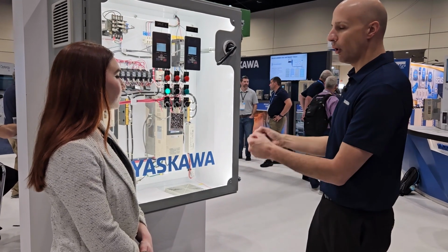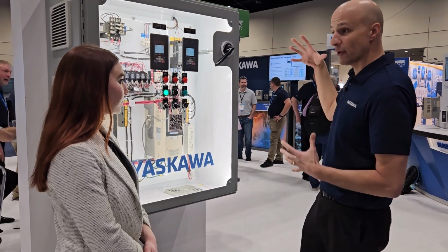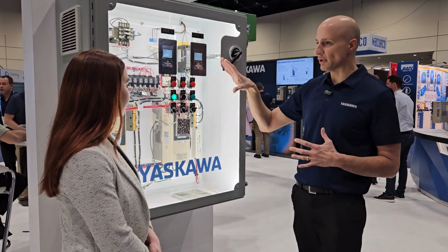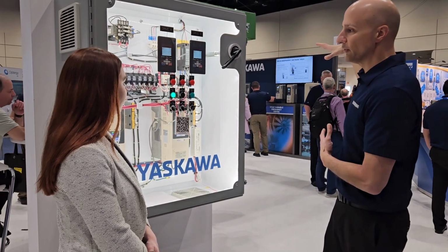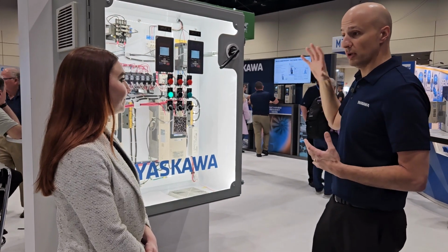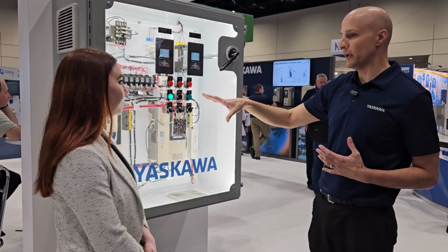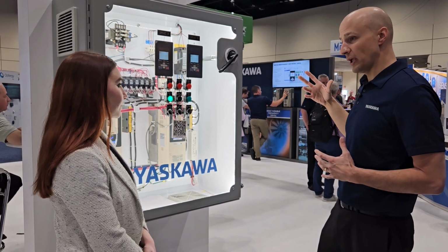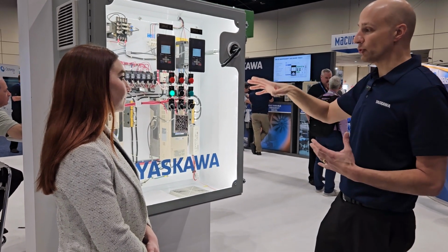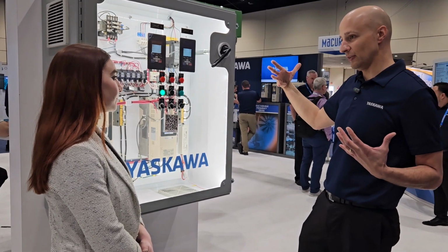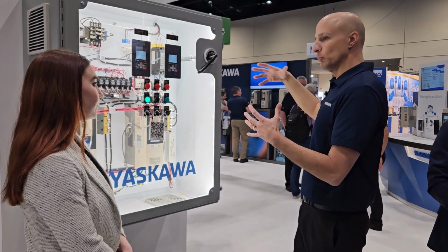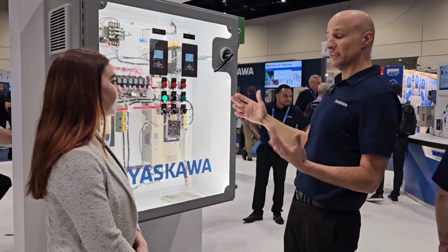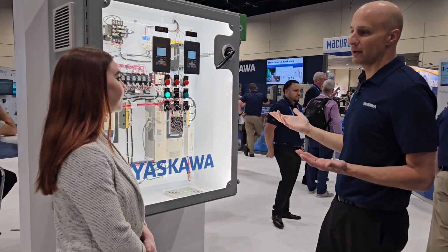So the customer lands all of the wiring for their fan wall or these multiple motors, and they have the redundancy. So this would be a critical application fan array. They can run this more than likely 24 hours a day, as long as they have power, even if one of the drives were to fail. And in that situation, if one or two of the fans were to go down, if it was sized appropriately, the drives could ramp up the additional fans to make up for system pressure, to maintain a certain system pressure. So it really gives you flexibility in your design, I would say.